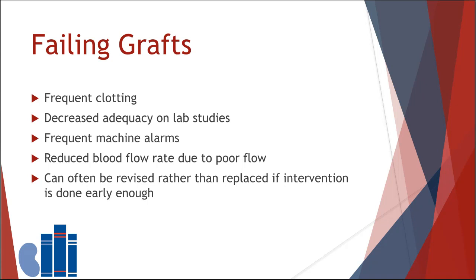Alarms on the machine were not invented just to drive people crazy. They signify when there's a problem. So when you're on dialysis, if your machine is alarming frequently and there are pressure problems, the vast majority of the time it's because there's a problem with your access. That's a good time to speak up to your nephrologist and say, my machine has been alarming a lot lately. I'm wondering if we need to have a look at my access and see maybe if it's developing a narrowing. The vast majority of the time, there probably is.